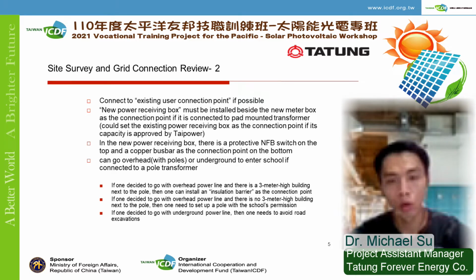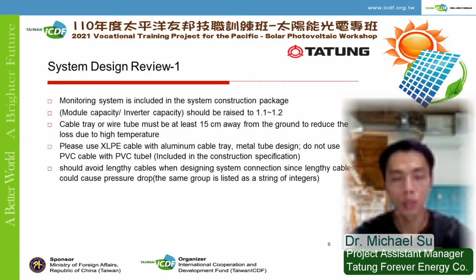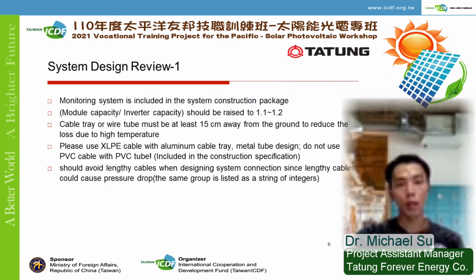If we do the connection directly to the transformer, our cable can either go overhead or beneath. Yet, as we have mentioned, we try not to go beneath since it requires too much work and time to dig up the roads. But of course, our choice would be based on the actual situation on site. Here are some regulations or suggestions for our system designing. For example, the cable tray must be at least 15 centimeters above the ground to avoid energy loss caused by ground temperature. These are some basic rules to follow while designing.